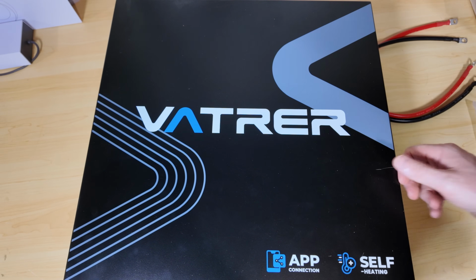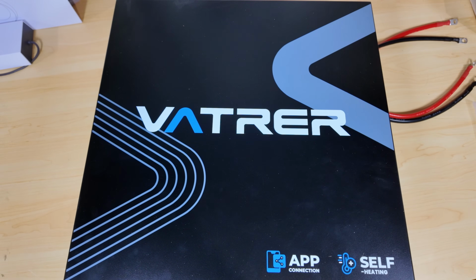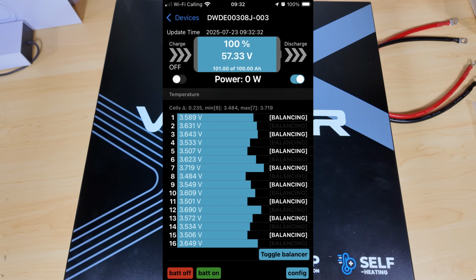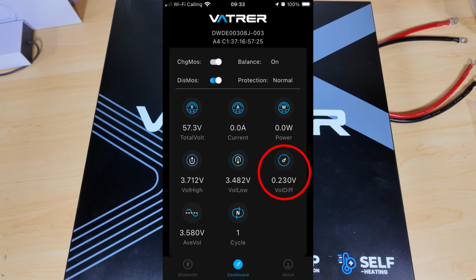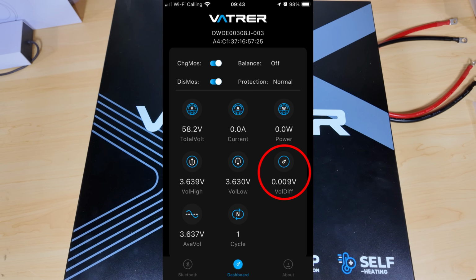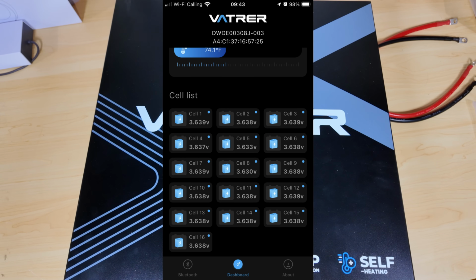As I mentioned a minute ago, I did perform a discharge test on this. I charged the battery to 100% and let it sit that way for at least 24 hours. You'll see here a picture from when I first got the battery charged to 100%, where the cells were not that balanced. I left it on the charger to balance, since this has balance while charging turned off. After 24 hours, it ended up balancing the cells really well, and you can see on screen the end cell differential and how well balanced they were after leaving them on that charger for 24 hours.